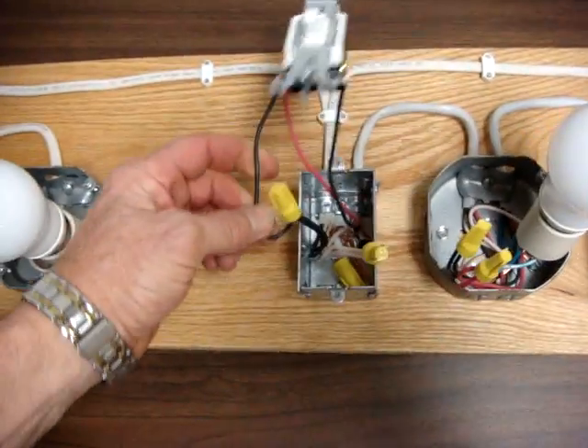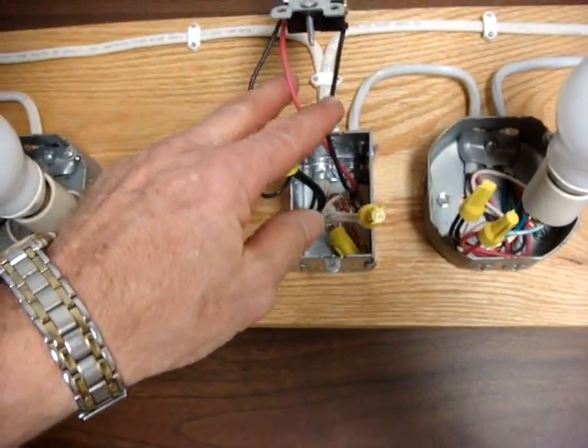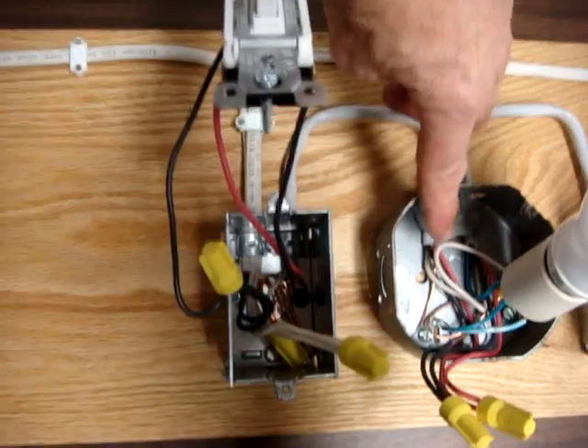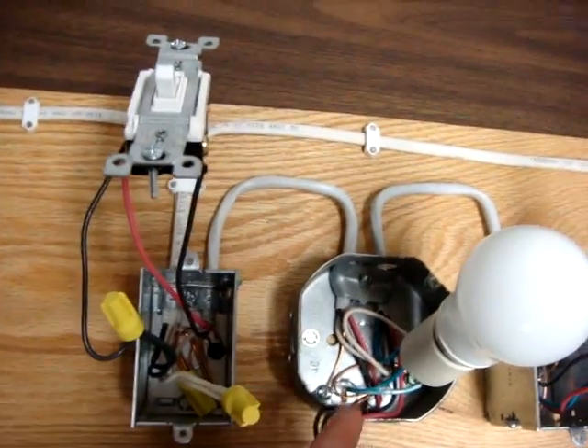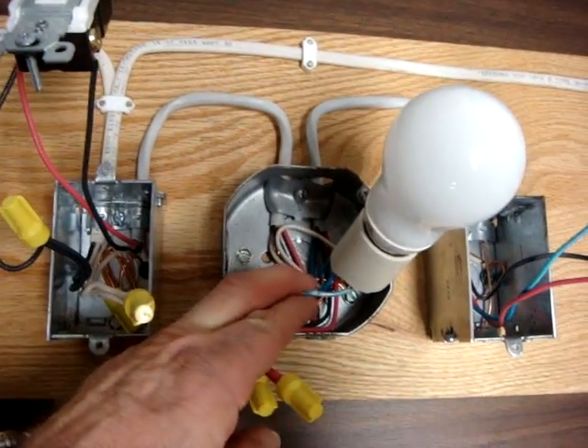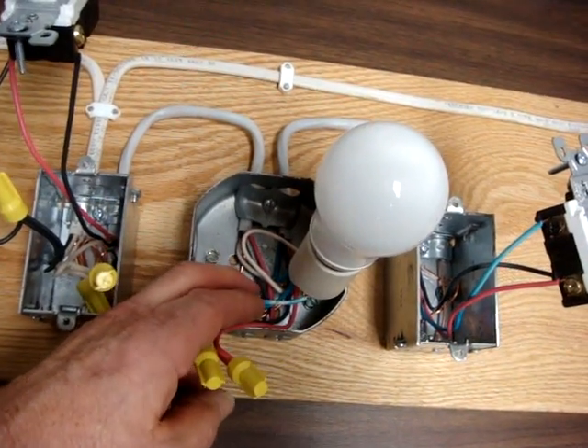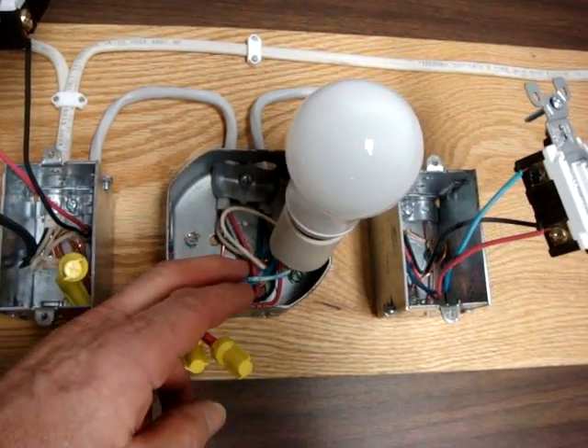In this particular case, the power comes in, comes through the travelers, through the light, and goes back out. Spliced the red and the black. And because the white is no longer a neutral conductor, or a current carrying conductor, it's part of the control system, I used a blue magic marker to color it a different color.